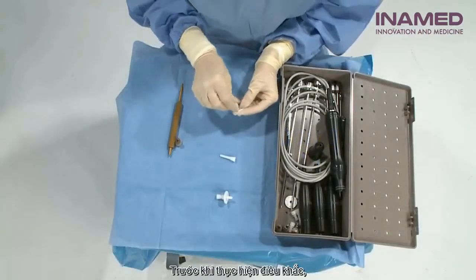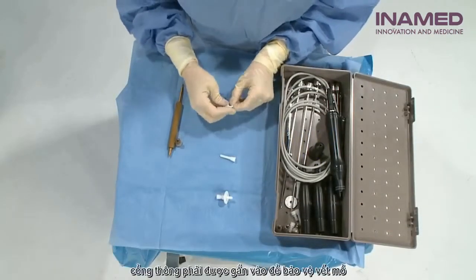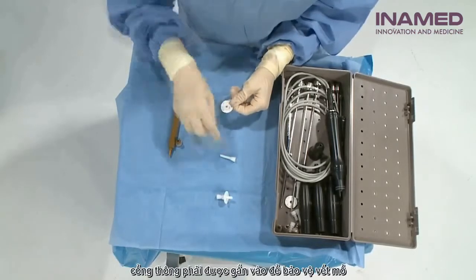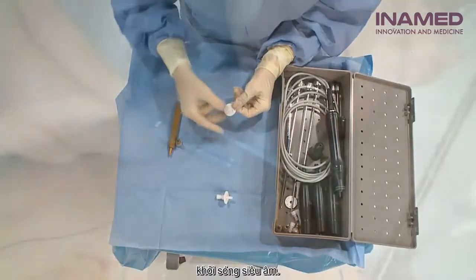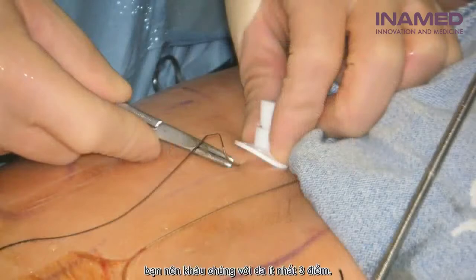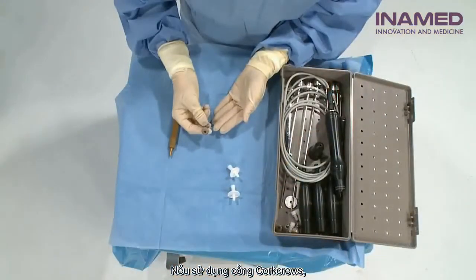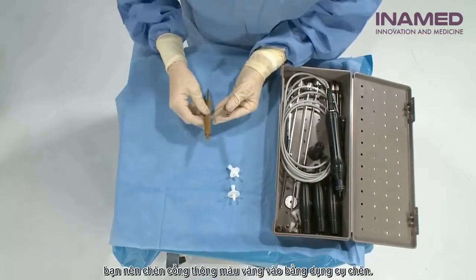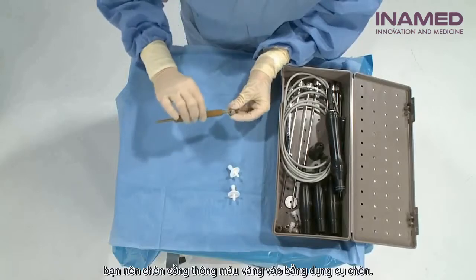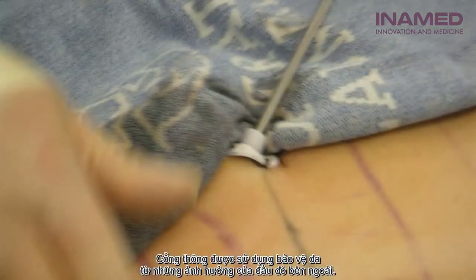Prior to performing actual contouring, skin ports must be inserted to protect the incisions from ultrasonic energy. If using the skin port discs, they should be attached with sutures anchored in at least 3 points. If using the skin port corkscrews, they should be inserted with the gold skin port insertion tool. Folded towels should be used to protect the skin from contact with the vibrating probe.